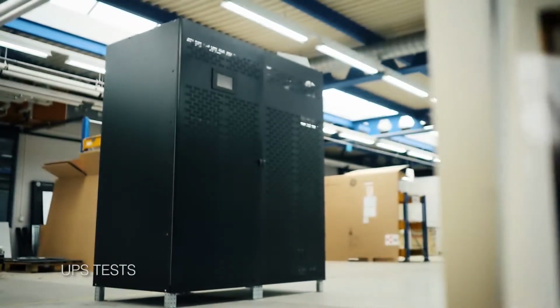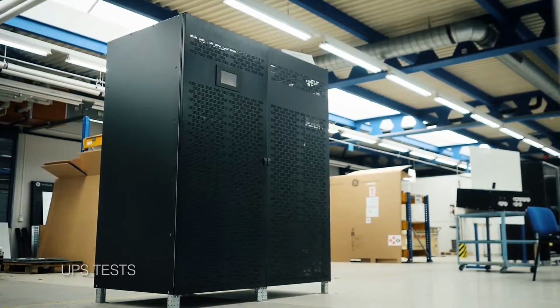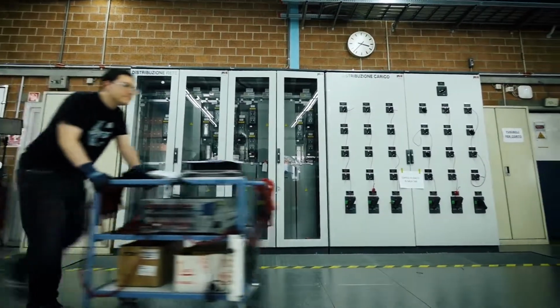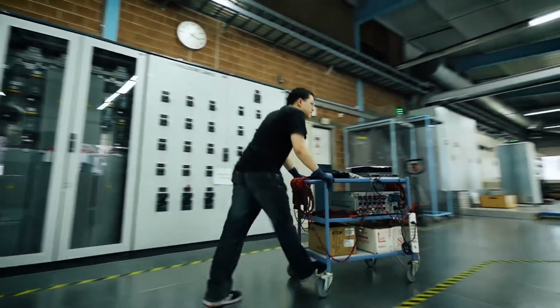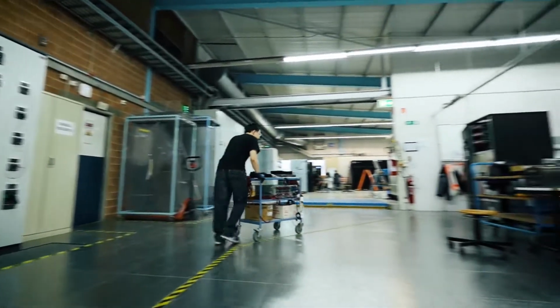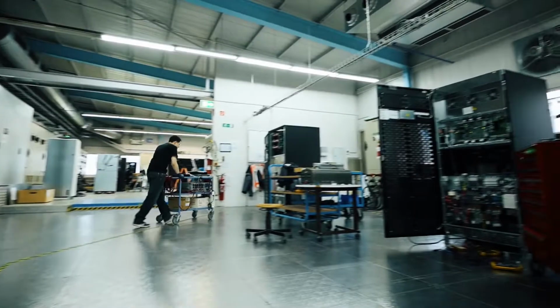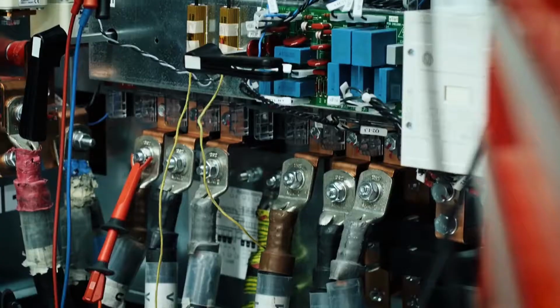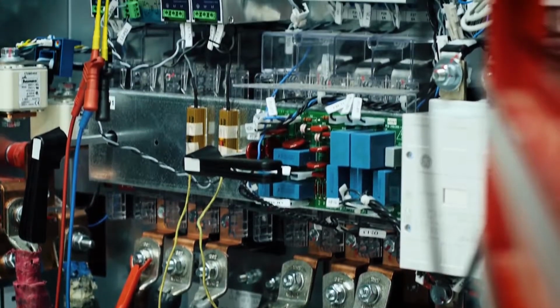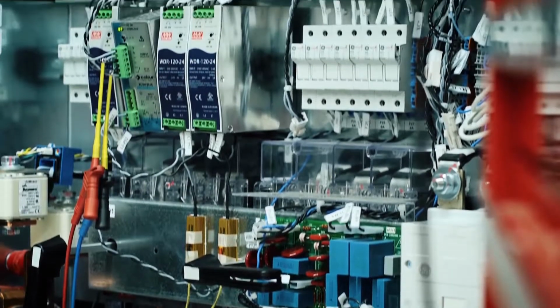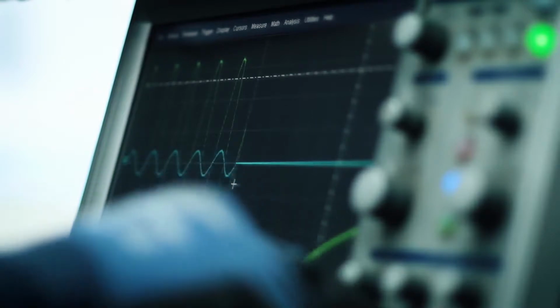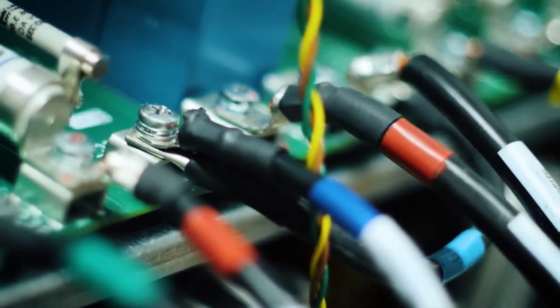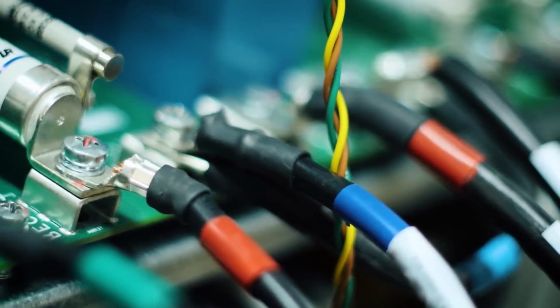Before the UPS model or prototype goes into production, it should pass a series of tests in specialized labs performed by qualified and experienced staff. The first test is on a sub-assembly stage. Such components as wires, PCBs and main modules should pass parametric tests. These tests last up to 40 minutes. All components are tested under a low voltage of 24 volts.